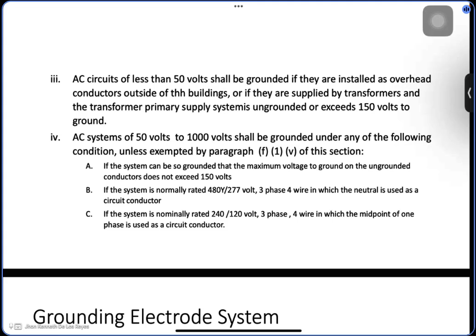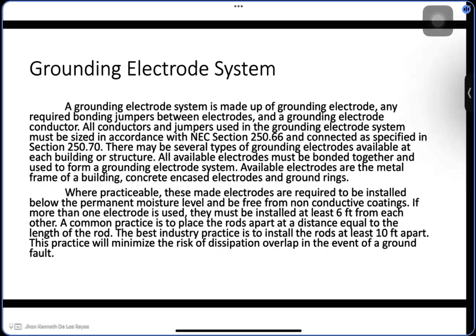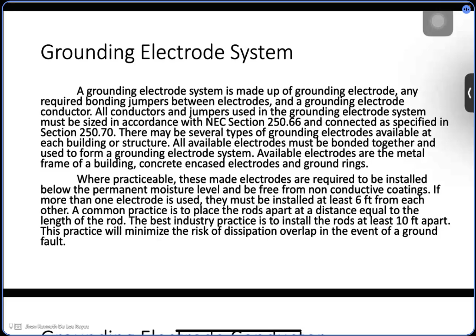Next is the grounding electrode system. Let's keep it short and simple. This includes ground rods, building steel, concrete-encased electrodes, and ground rings. All available electrodes must be bonded together. There are spacing rules: minimum of 6 feet apart, but best practice is at least 10 feet apart. You can't go below the minimum standard, only above it.